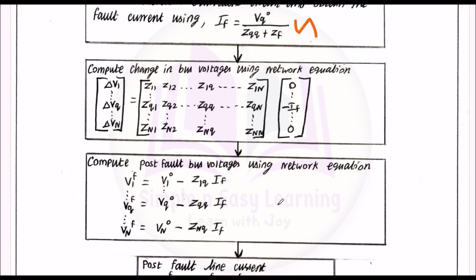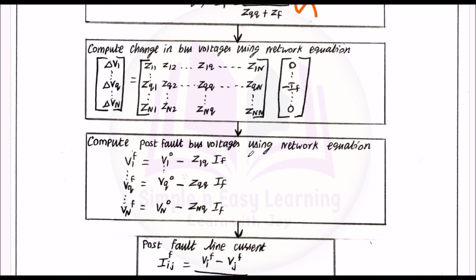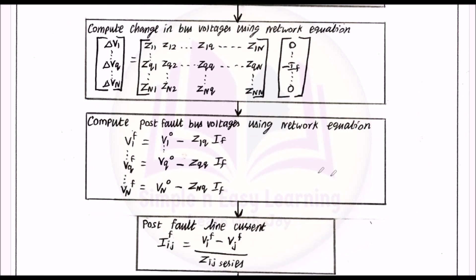Next step: compute post-fault bus voltages using the network equation. After the fault, the post-fault bus voltages are determined using: V1f = V10 minus Z1q × If, V2f = V20 minus Z2q × If, up to Vnf = Vn0 minus Znq × If, where q represents the fault bus.